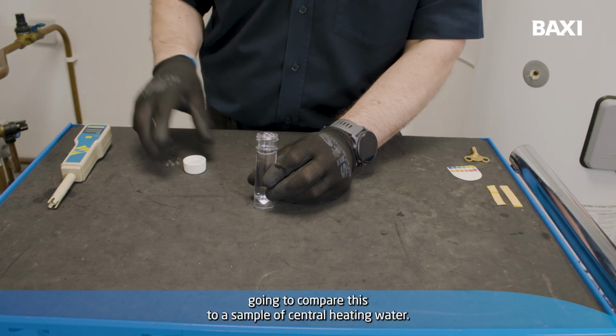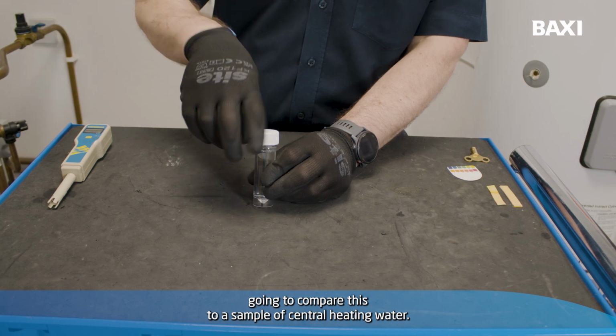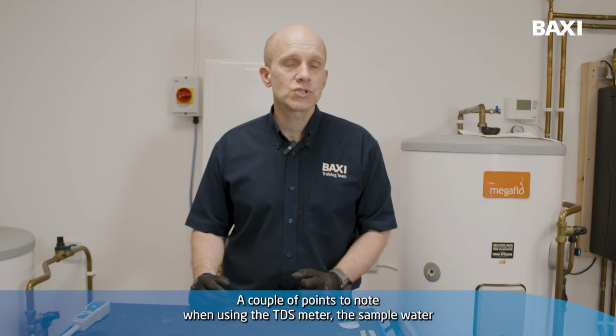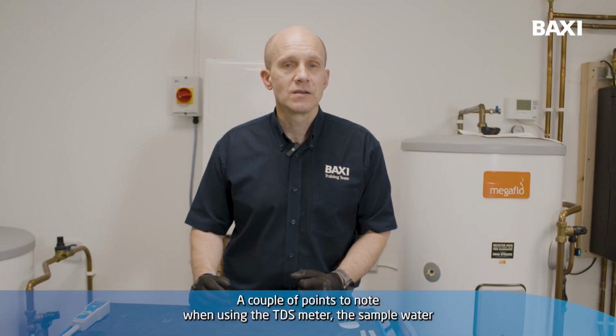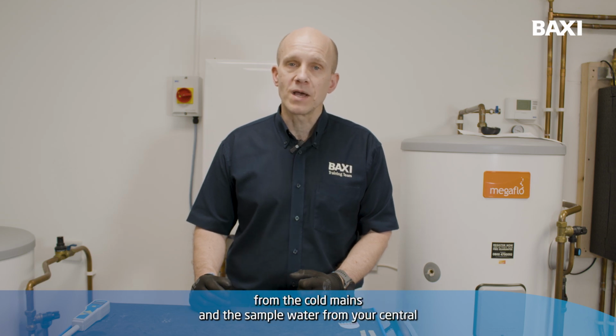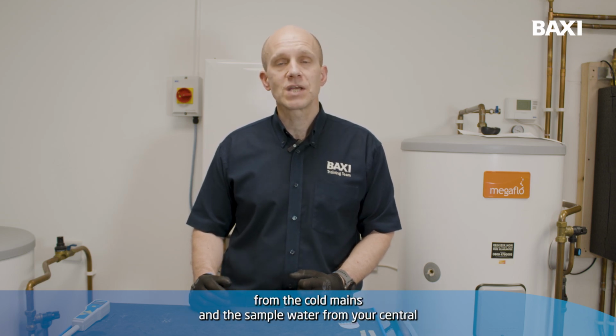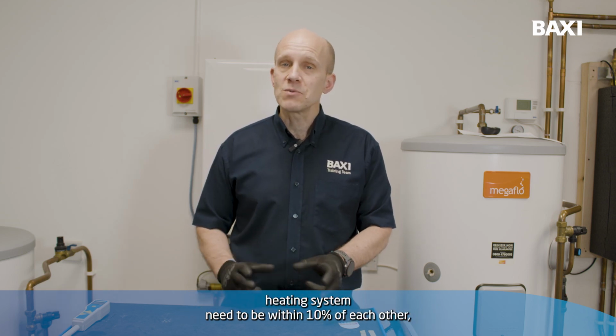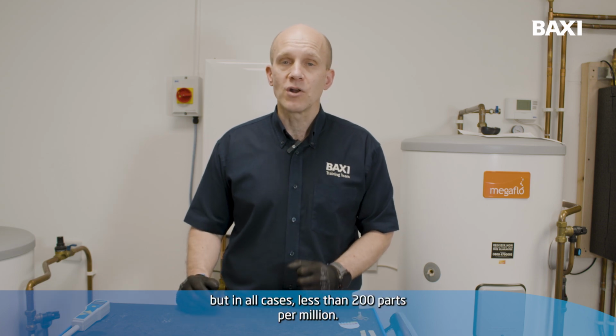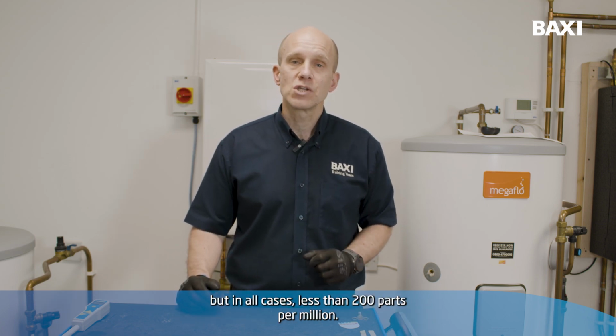I'm now going to compare this to a sample of central heating water. A couple of points to note when using the TDS meter. Your sample water from the cold mains and the sample water from your central heating system need to be within 10% of each other, but in all cases less than 200 parts per million.